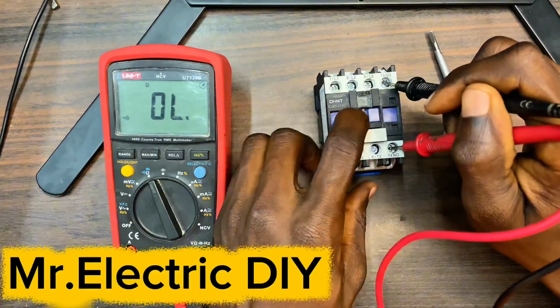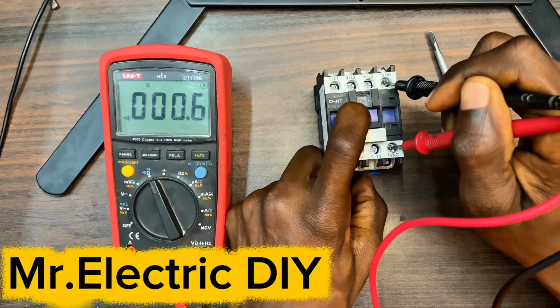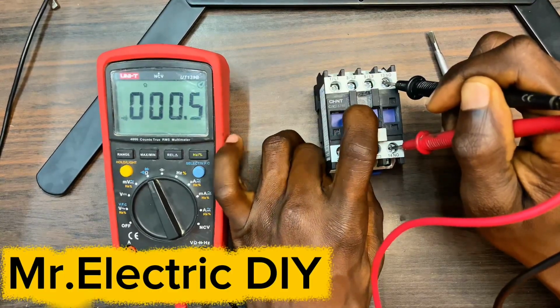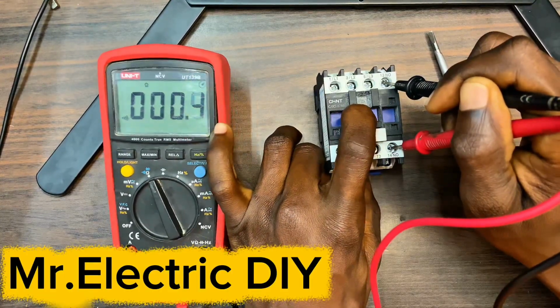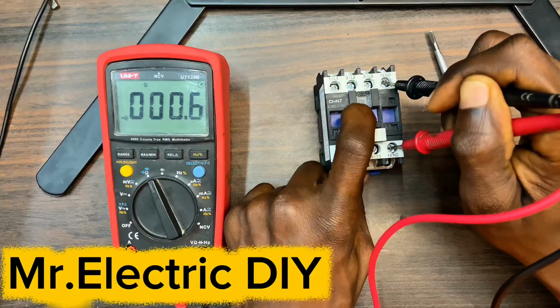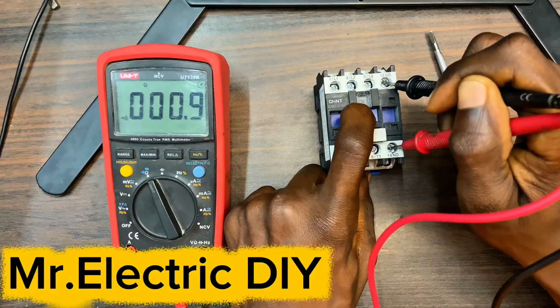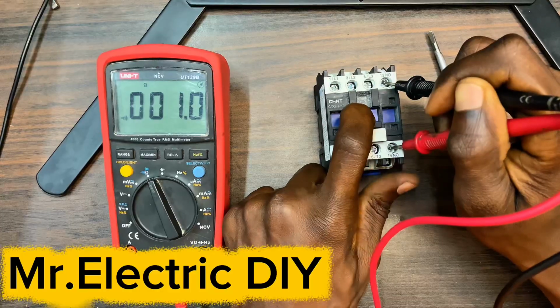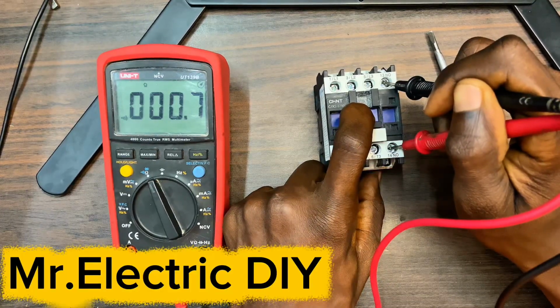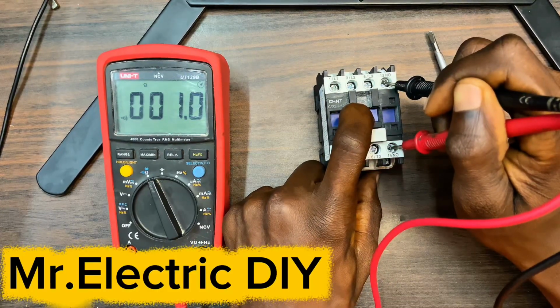Hold it, push the plunger. Okay. It is beeping, and also there's a reading on the meter telling us that this normally open contact is also in good condition.